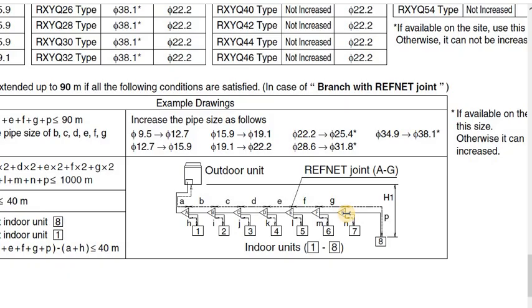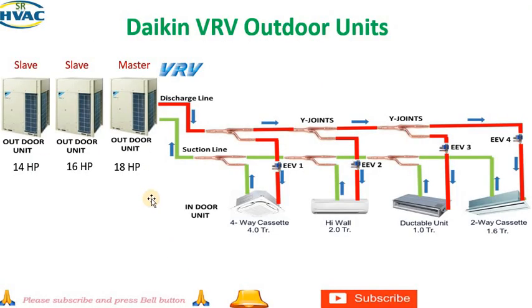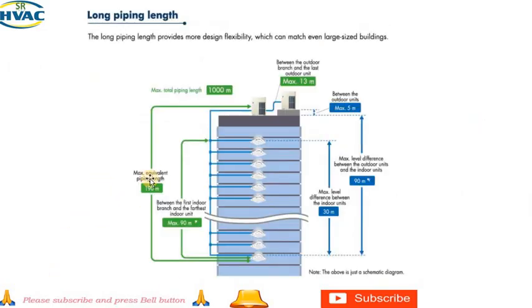So from here to here you have to increase the diameter. You don't have to increase the indoor size. Suppose this one is 9.5, it will be increased to 12.7, it will be half inch. This one is 15.9, it will be increased to 19.1. If it is 22.2, it will be increased to 25. By following this method, you can increase your pipe length above 40 meters if there is a requirement. Okay friends, I hope you understand. It means you have to increase the pipe diameter, not the length. So you can go up to 90 meters that we have discussed earlier.